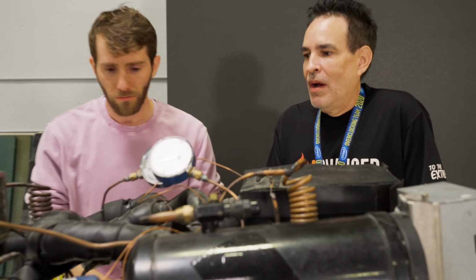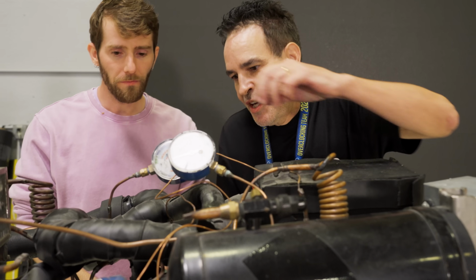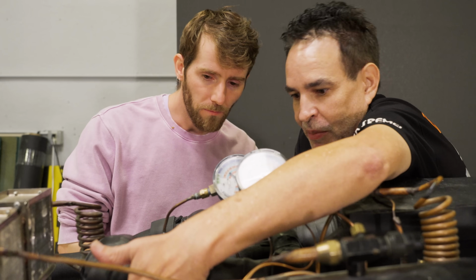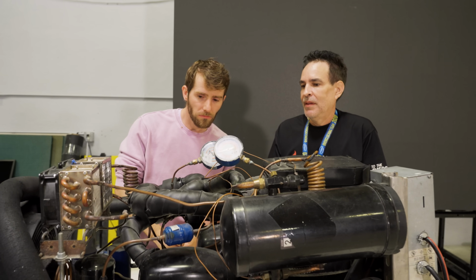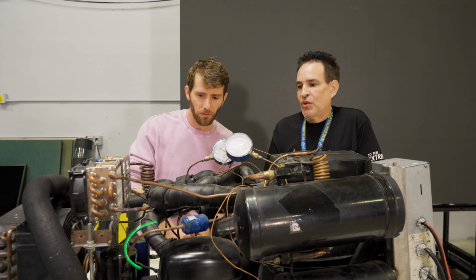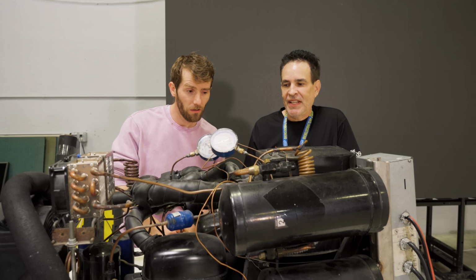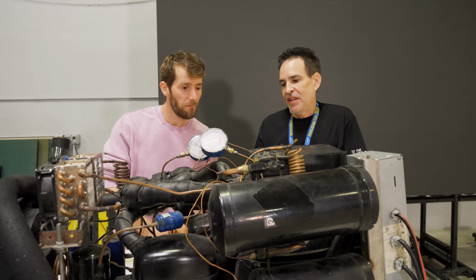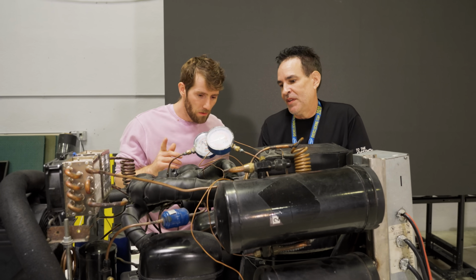Okay, so right now we just got to wait a few minutes and watch for some ice buildup on the first stage. The ice will build up right here on the back side of the suction line. Once we get a little bit of ice built up on there, we can fire up the second stage compressor, and we watch for the same thing—a little bit of ice building up on the back of the second stage compressor.